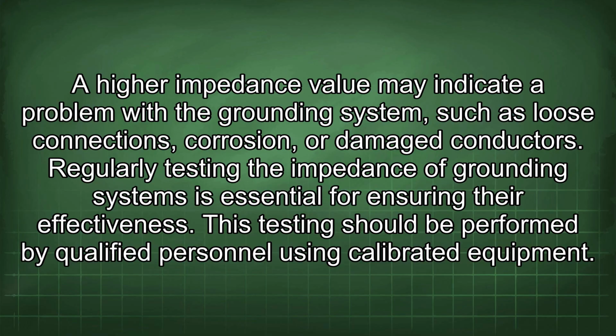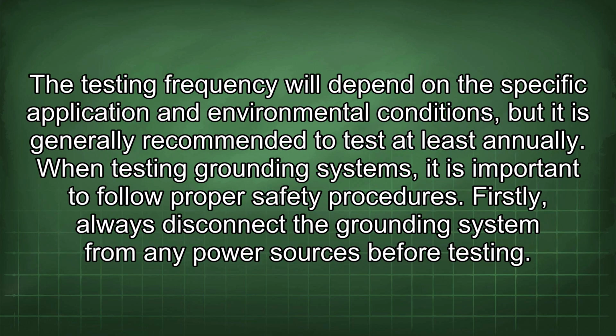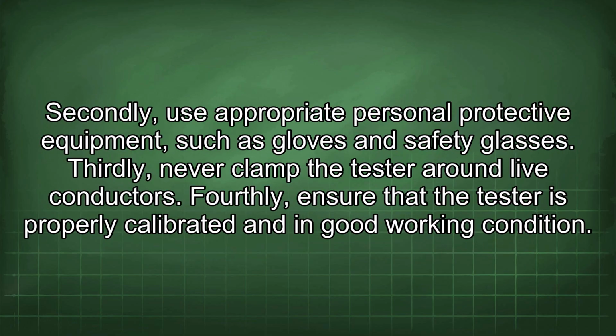This testing should be performed by qualified personnel using calibrated equipment. The testing frequency will depend on the specific application and environmental conditions, but it is generally recommended to test at least annually. When testing grounding systems, it is important to follow proper safety procedures. Firstly, always disconnect the grounding system from any power sources before testing. Secondly, use appropriate personal protective equipment, such as gloves and safety glasses. Thirdly, never clamp the tester around live conductors. Fourthly, ensure that the tester is properly calibrated and in good working condition.